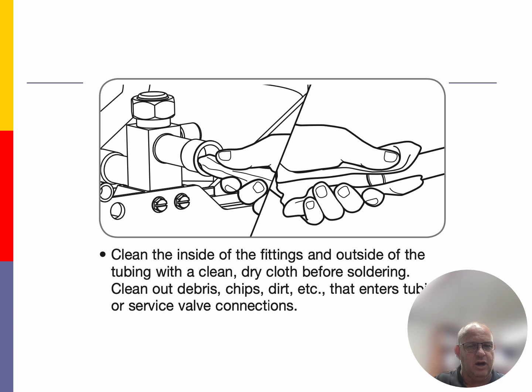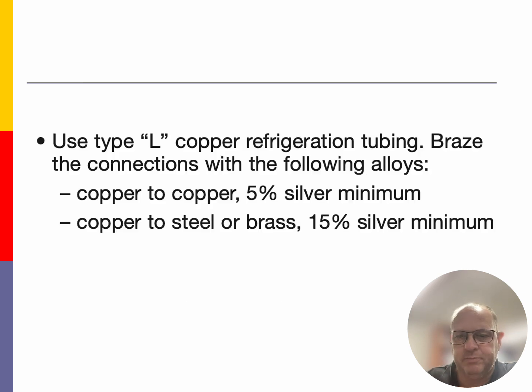Keep any chips, debris, metal fragments out of the pipe. We don't want anything on the inside of it. These orifices in these metering devices are very, very small and they will plug up. So be sure that you're keeping dirt and any foreign material out of this pipe as you are hooking it up. We want to use type L copper. It's a thicker copper. It's ACR copper.